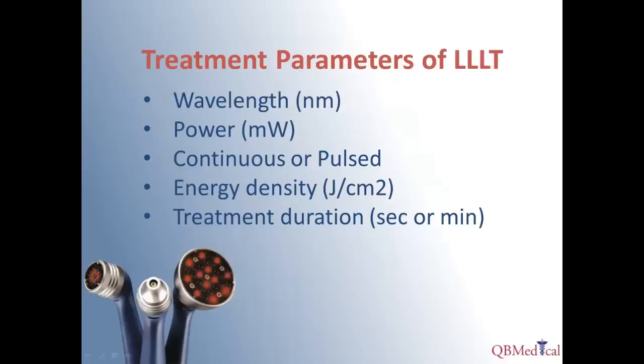Now let's look at some specific treatment parameters. Among these, we have wavelength, measured in nanometers; power, measured in milliwatts; continuous or pulsed, which is referred to as the duty cycle; the energy density, measured in joules per square centimeter; and the treatment duration, typically measured in seconds.